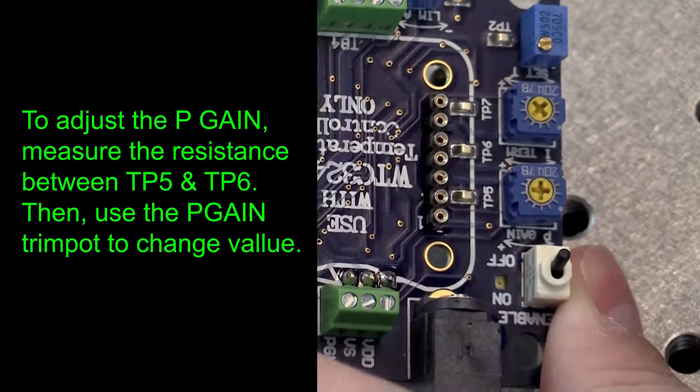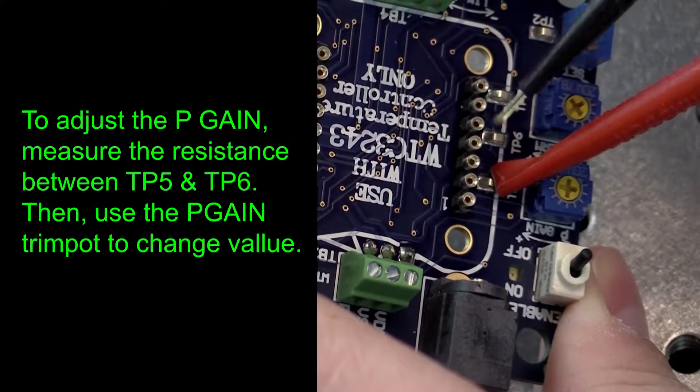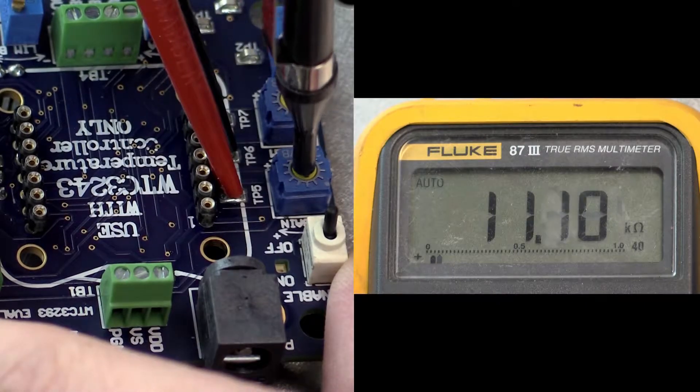To adjust the P-gain, use an ohmmeter to measure the resistance between test points TP5 and TP6. Adjust the P-gain trim pot to the calculated resistance.